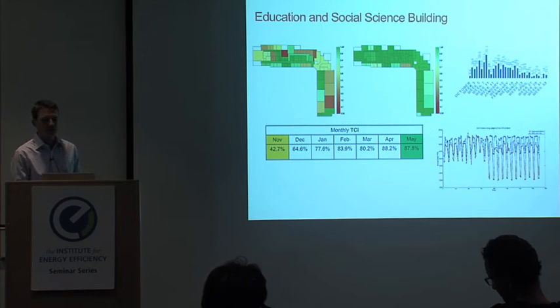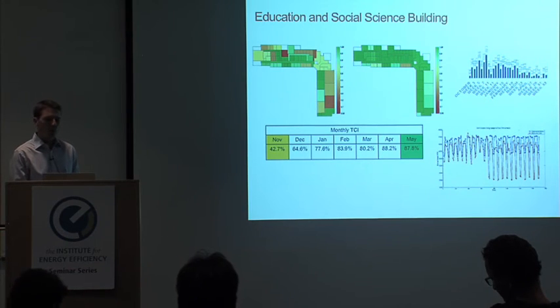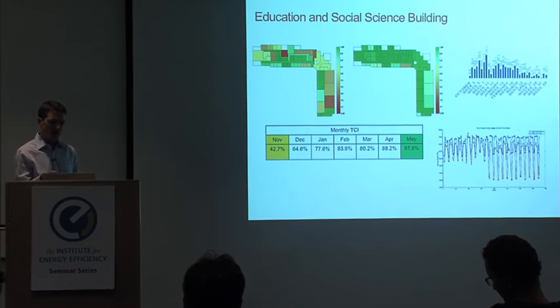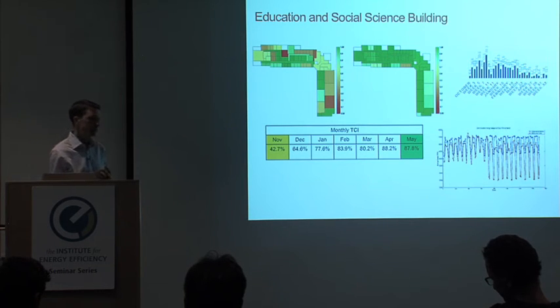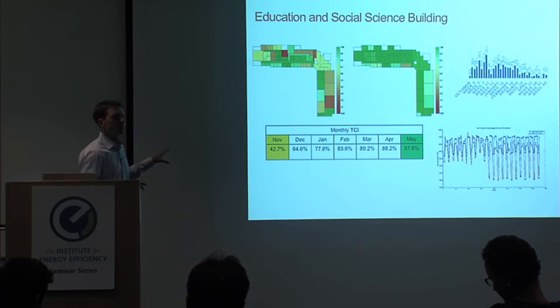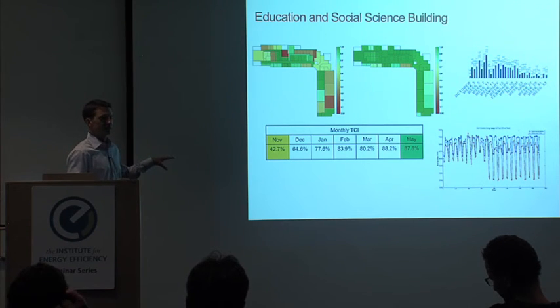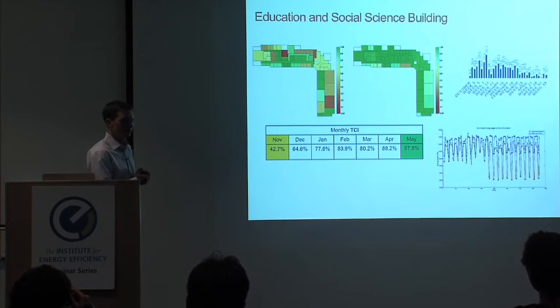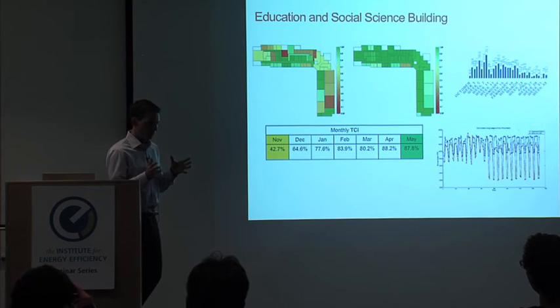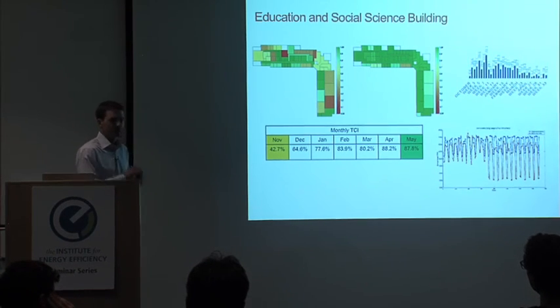Yeah, absolutely. I'd ballpark the savings we got out of this building at about 15%, maybe a little less on the electricity side. One thing we were doing at this building was starting the heating system at 3 in the morning - the building got built, people complained it was too cold in the mornings, so we took those anecdotes and said, okay, we'll be conservative and start at 3 in the morning.